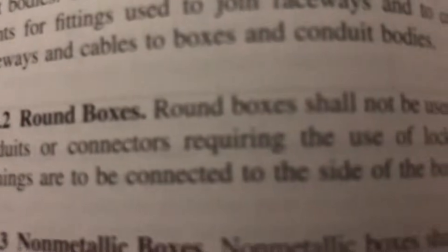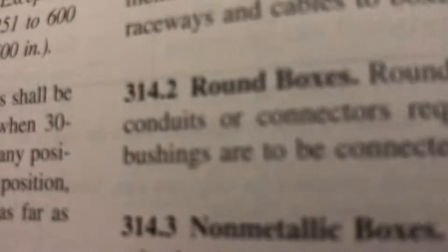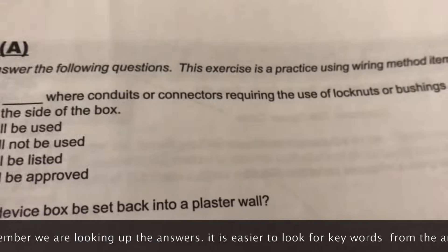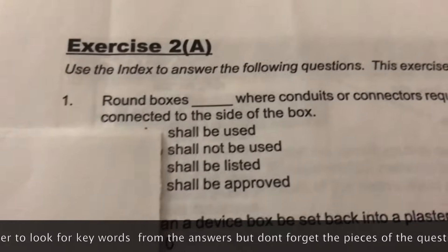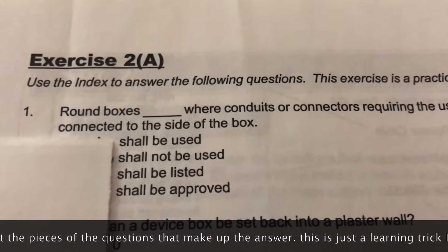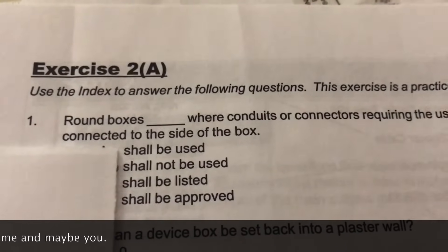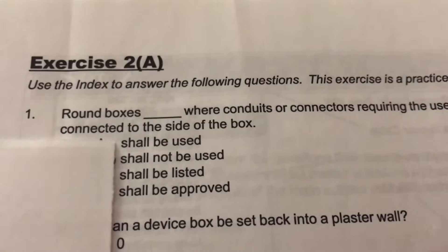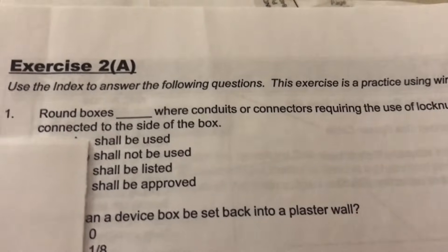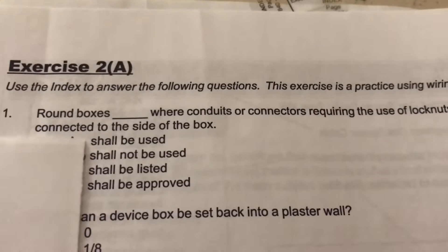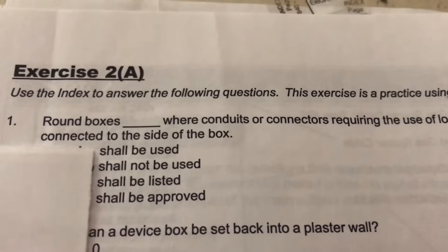We found it — 'Round boxes shall not be used where conduits or connectors requiring the use of lock nuts or bushings are to be connected to the side of the box.' So the answer is 'shall not be used.' Going back to our answer choices, that matches exactly. It's pretty easy — look up 'boxes' in the index, find Article 314, scan the article, find 'round boxes,' then match your keywords like 'shall not be used.' That's your first lesson in looking up code book answers.